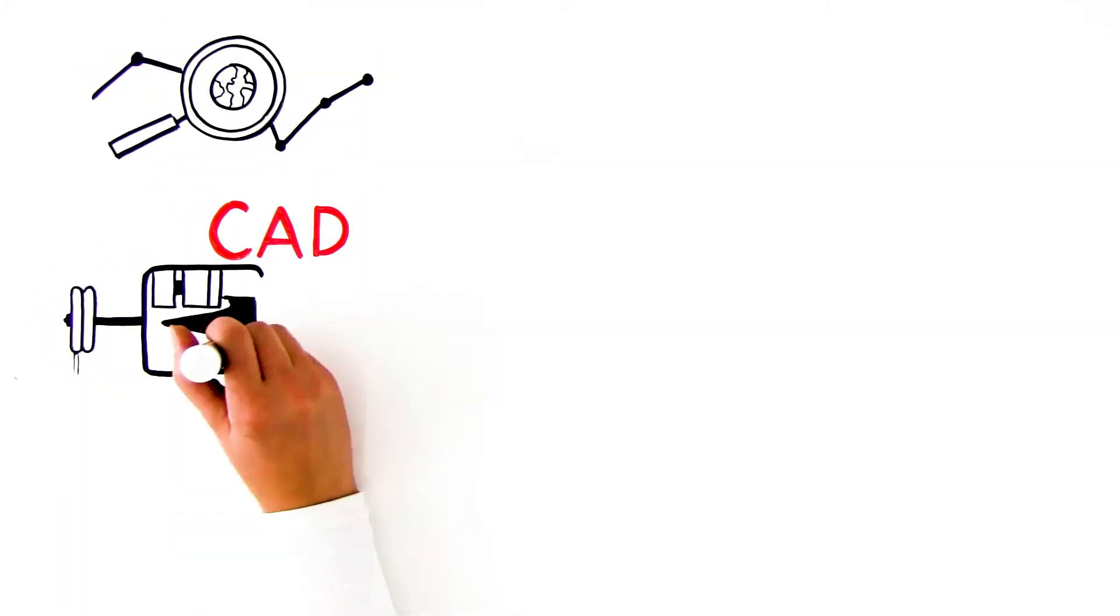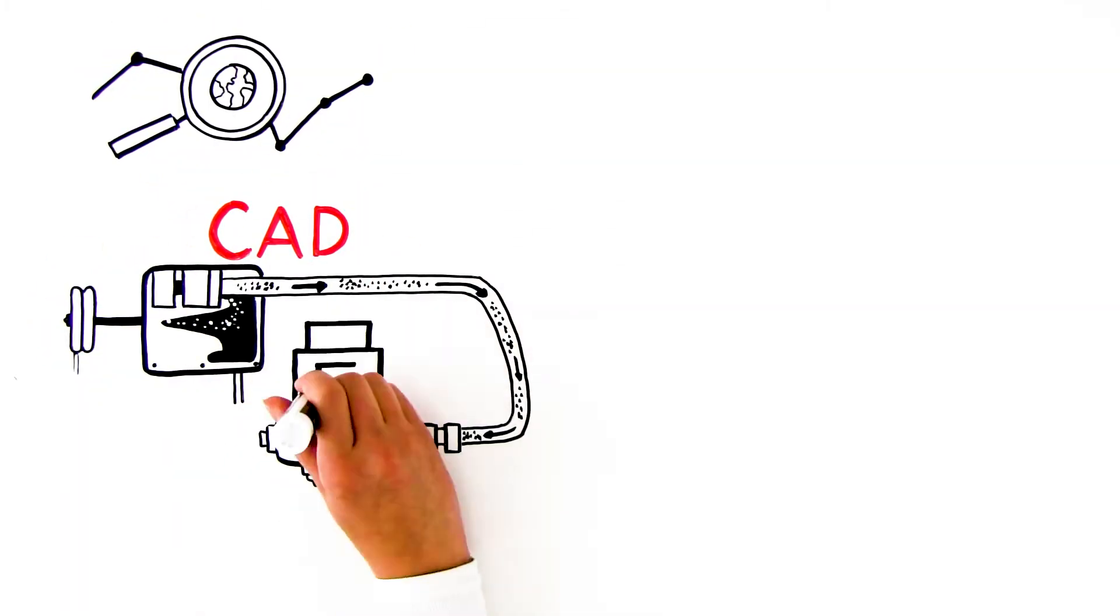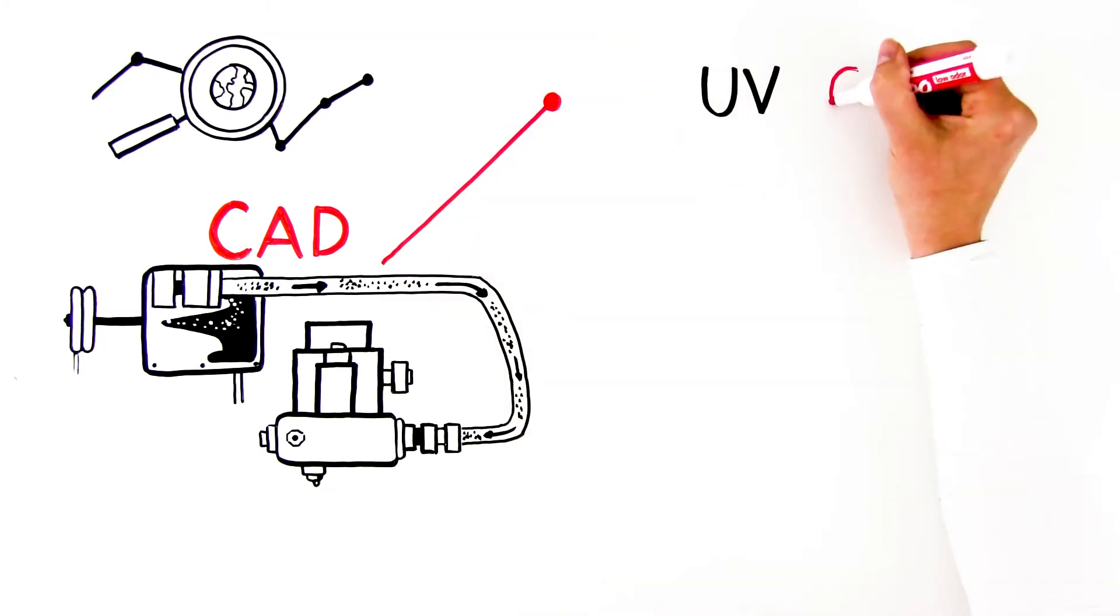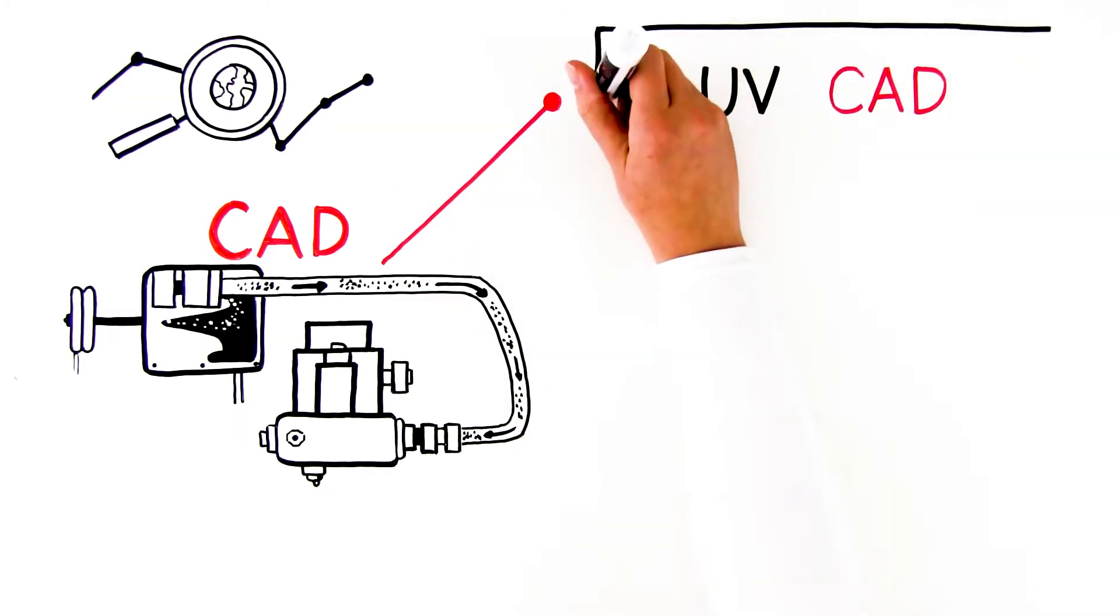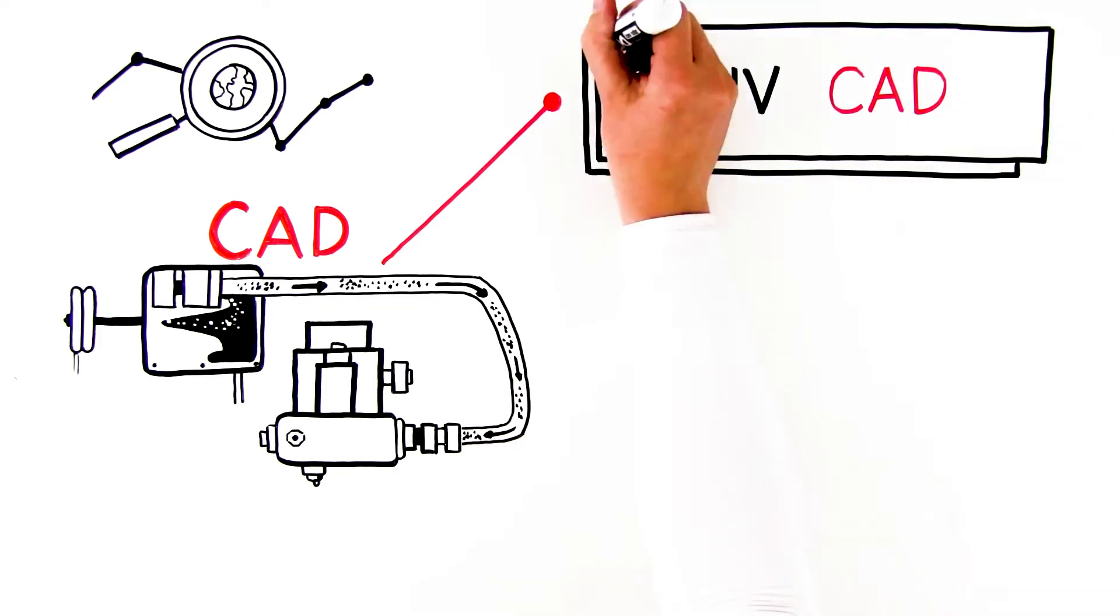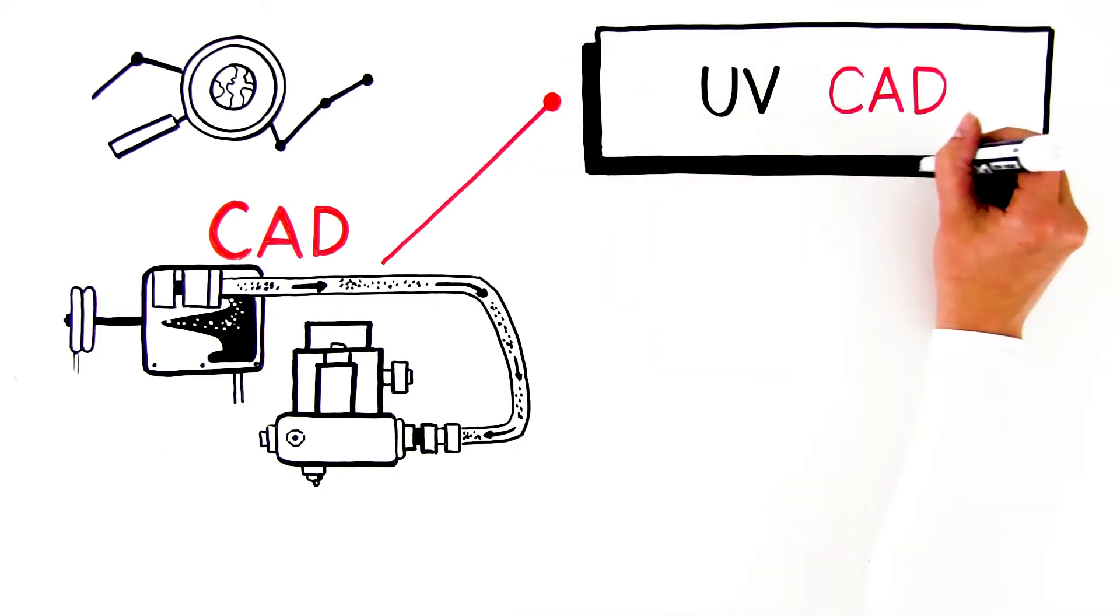The best part is you don't have to choose one detection method over another. Because CAD is a universal detector, you can use it to complement your HPLC UV analysis in a situation where excipients in a formula are a mix of UV-active and inactive components.